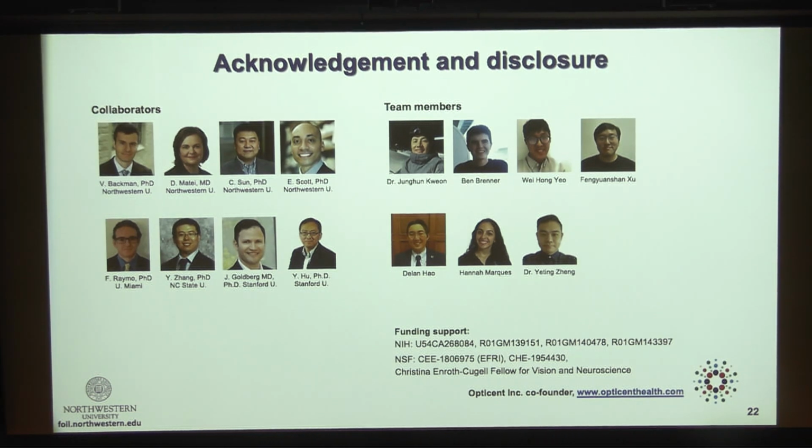All right, the question is, what's the spectral resolution? The spectral resolution is a trade-off between spectral precision and spectral resolution. High spectral resolution means we have to spread the photons into more pixels, where each camera CCD element will see fewer photons, and that's a noise limited process. So it depends on the actual need. If you are talking about quantum dots, the photon budget is unlimited, so go as high as you want. But if it's Alexa fluor, the rule of thumb is 5-ish nanometers.